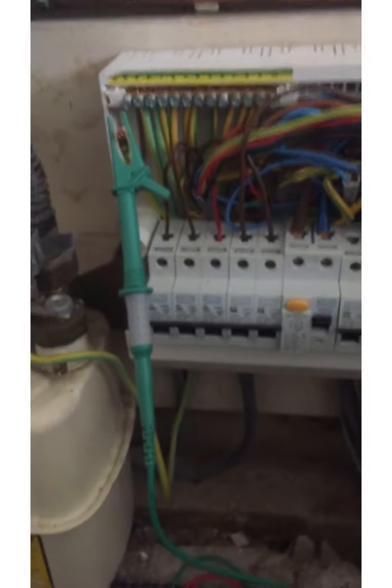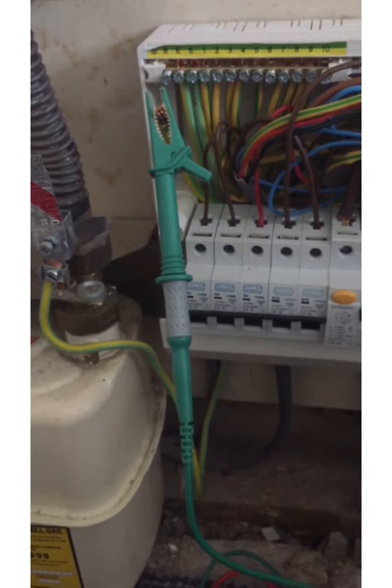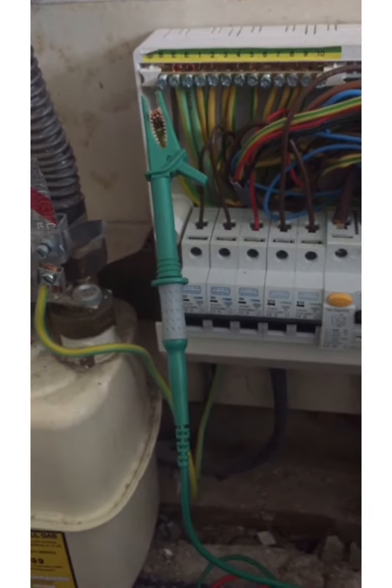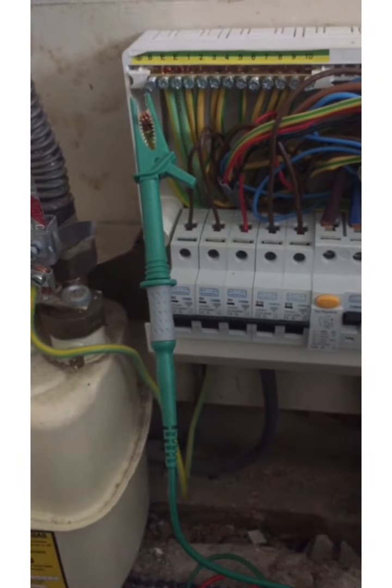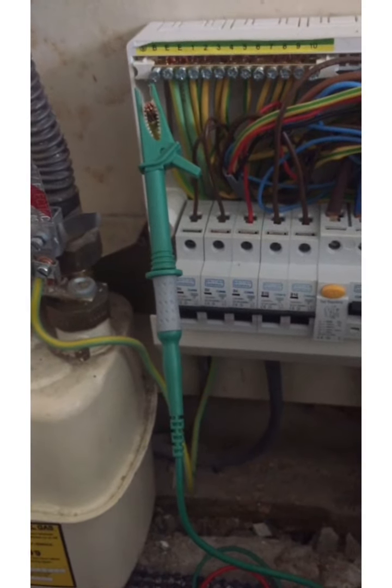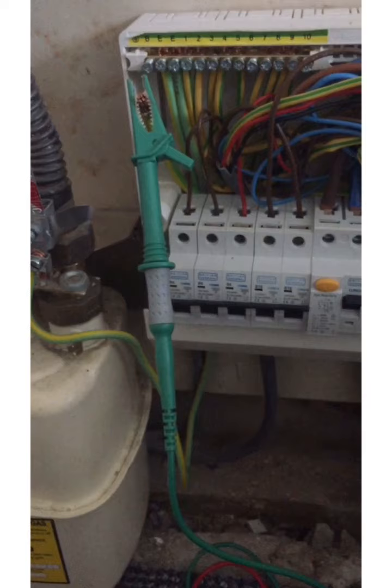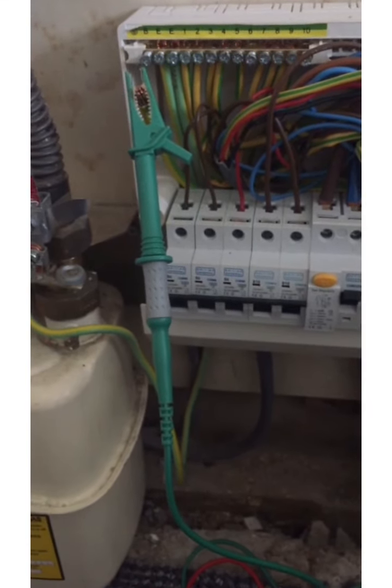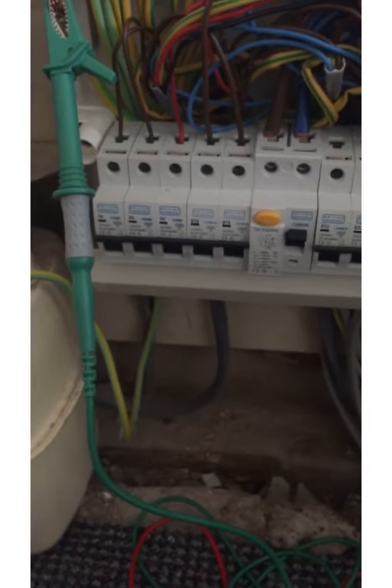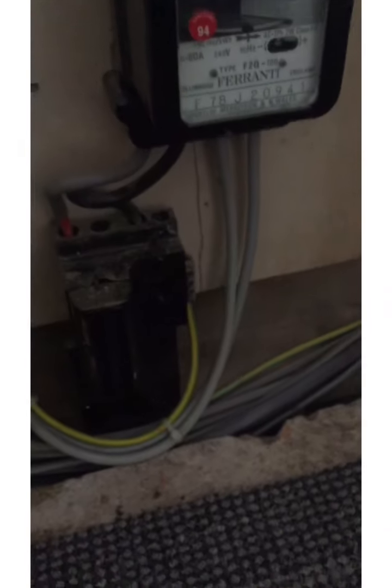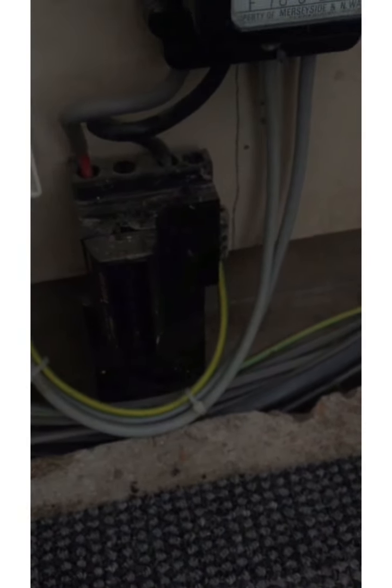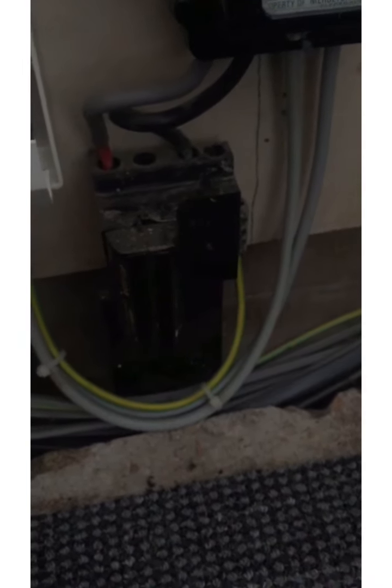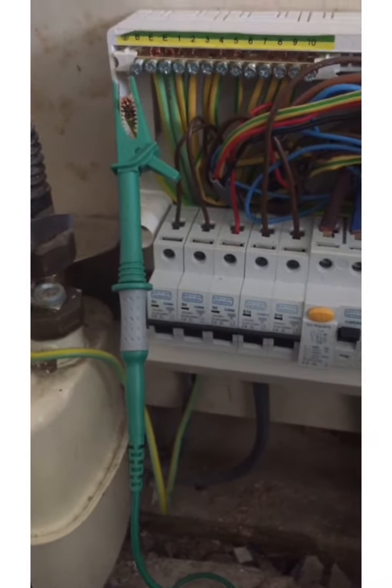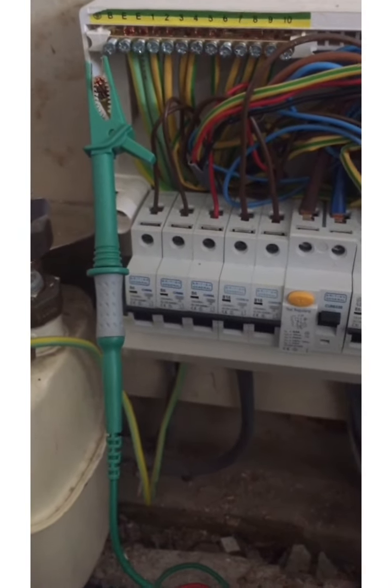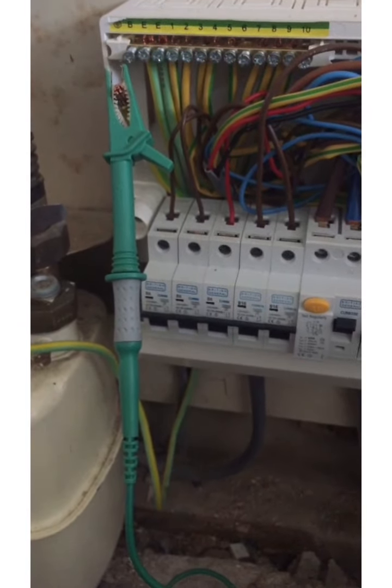Sometimes people say to me, well, there's no point in disconnecting that earthing conductor from the means of earthing, because I'm getting the same value whether it's connected or disconnected. I've just tested that for myself again, just to run through that, and indeed, I was getting the same value whether it was connected or disconnected. But what I say to people is, if we haven't got a bona fide means of earthing, then you can bet your bottom dollar you get a different value, because if we don't have a proper earth coming in, we're going to get open circuit. So you would get open circuit when the earthing conductor is disconnected, and you get what's called a fortuitous value, or a fake value, if you like, for ZE when the earthing conductor is connected, because obviously you're getting it through all the parallel paths.